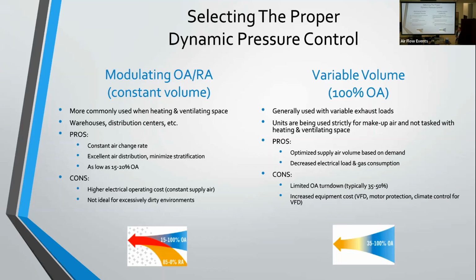Not to say that there isn't, honestly, what I might see happening soon is you see both, where you'll see an outside air and return air unit with the VFD. A lot of times that's used in an unoccupied setting or in a heating season. You might run the unit at a lower air volume in an unoccupied mode and set it up for the minimum amount of outside air. And then if you have an occupancy setting, you can run that unit at a higher air volume to meet that demand. So you might see a hybrid that might be more popular coming down the road. Going off memory, I would say we see more outside air return air units. Good deal.